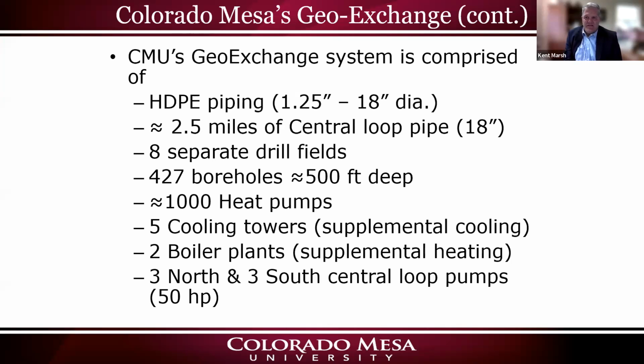Our system is comprised of, as I mentioned, 18-inch diameter HDPE pipe down to 1.25 inches. We've got a lot of areas with 10 and 12-inch diameter pipe, depending on the load of that part of the system. We like to keep the flow rate within the pipes at or below 5 feet per second to keep friction loss as low as possible. We have about 2.5 miles of central loop piping, if you can believe that. It seems like a huge number, but we have a lot of it on campus.